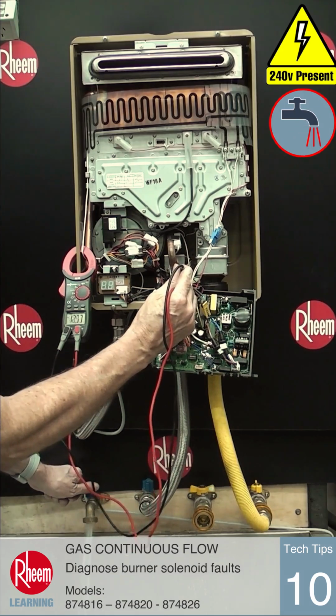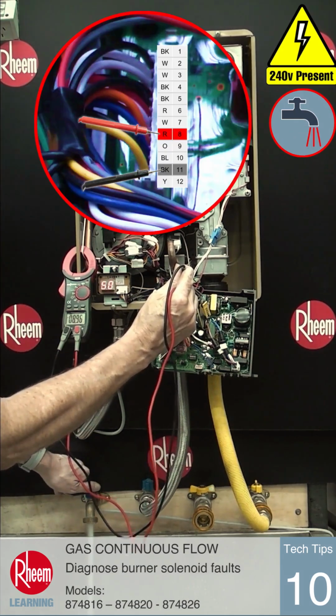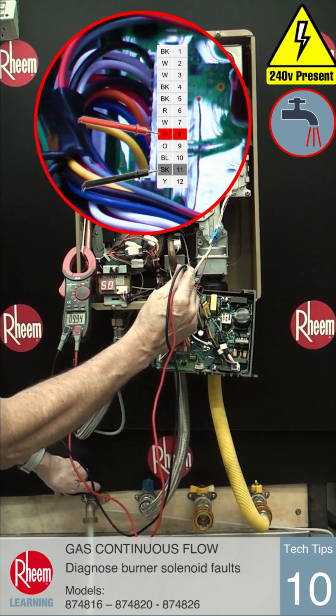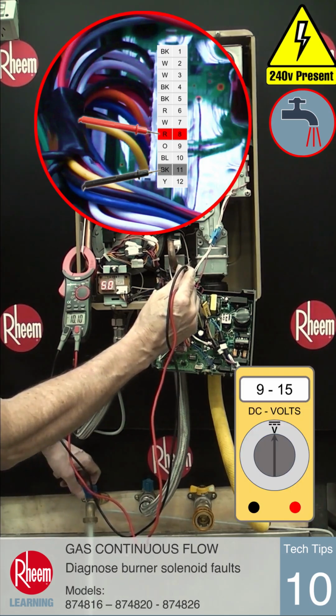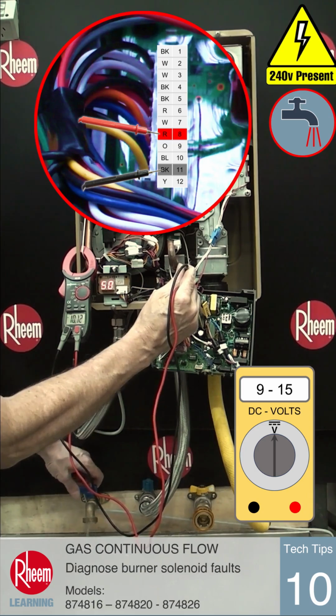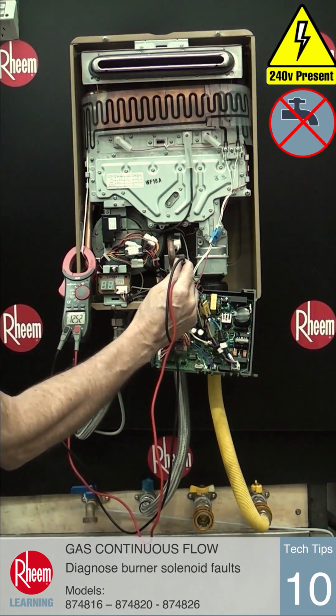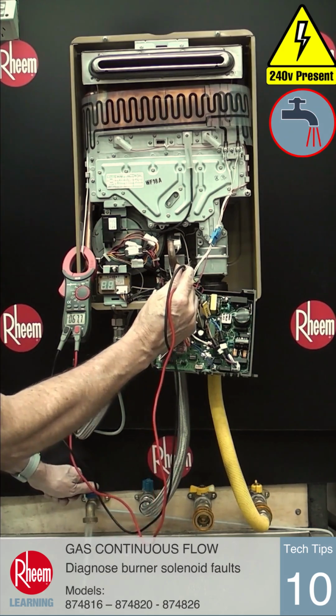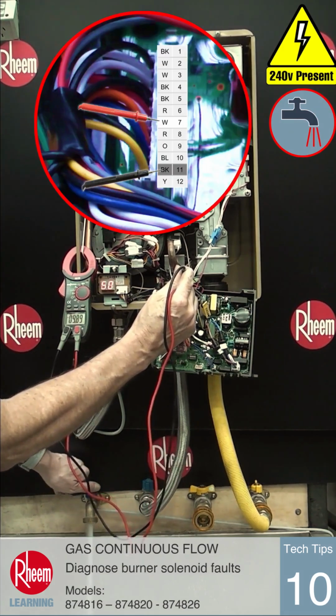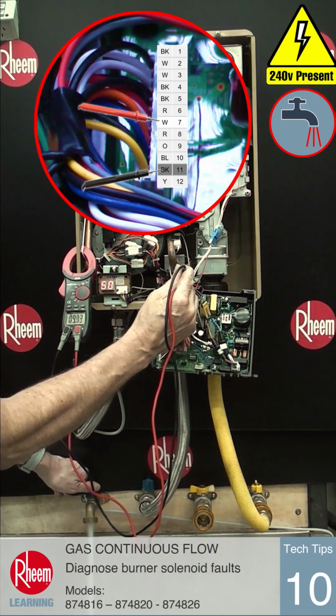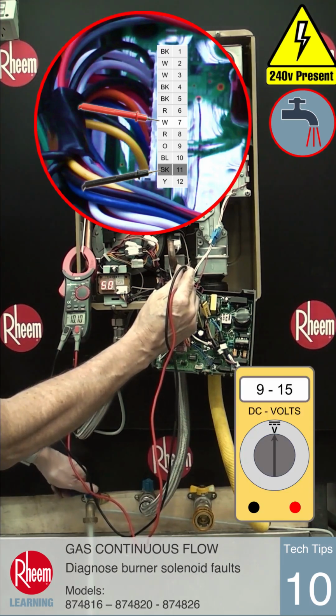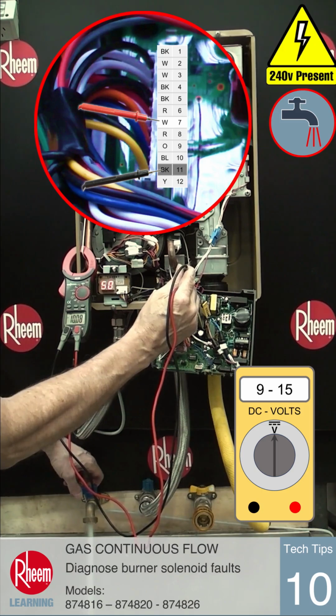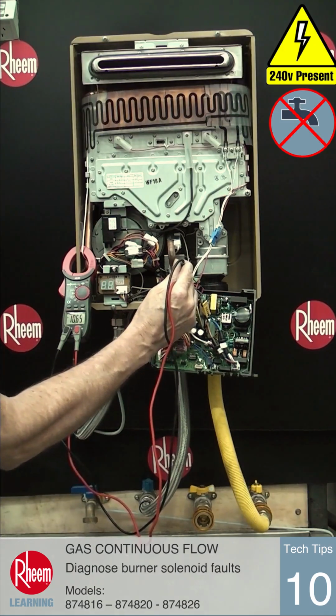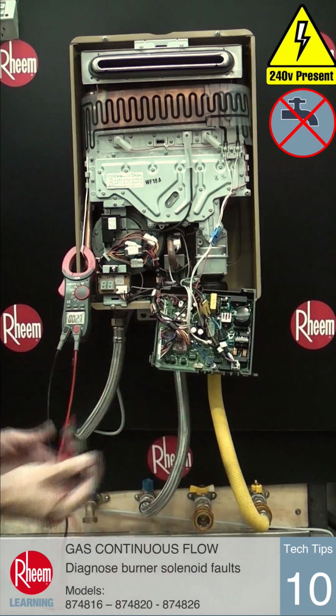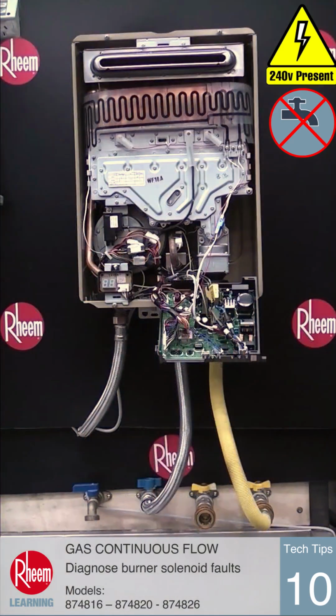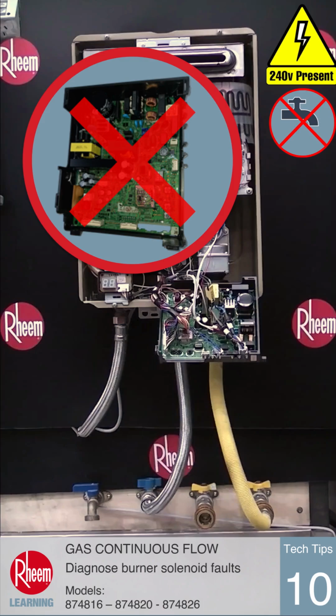Repeat the test for solenoid 2, this time between pin 11 black and pin 8 red. The reading again should be between 9 and 15 volts DC. And finally, to test solenoid 3, this time between pin 11 black and pin 7 white, and the reading will also be between 9 and 15 volts DC. If there is an incorrect or no voltage reading for any of these tests, the PCB is faulty and should be replaced.